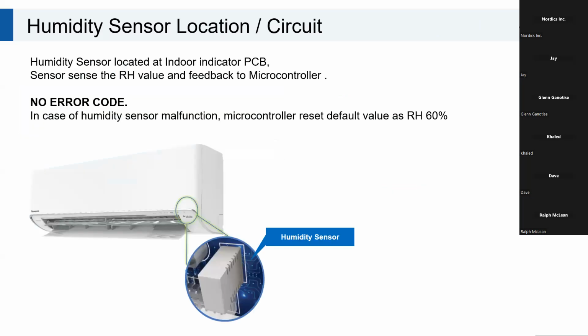So now there is a trick. This humidity sensor is located on the right side at the bottom, as you can see on this picture inside. And it's part of the PCB board, which has the indicators. So if it goes faulty, there is no error code generated. So how do we know if something is faulty? Actually, we will not know.